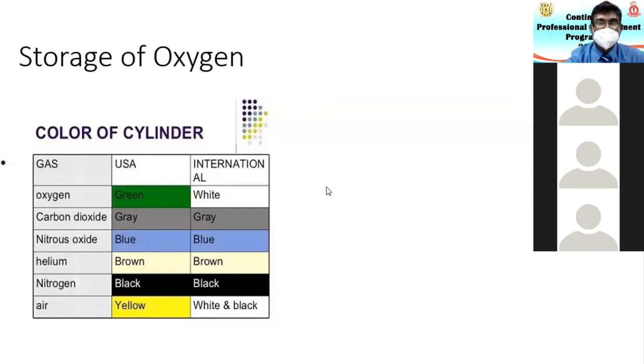So you can see this J cylinder, 57 inches. It has a capacity of 6,800 liters. Sometimes we use high flow nasal oxygen. That is the most used oxygen device nowadays for COVID. But unfortunately, it uses a lot of oxygen. So if you use this J cylinder for high flow nasal oxygen, it uses about 60 liters per minute.